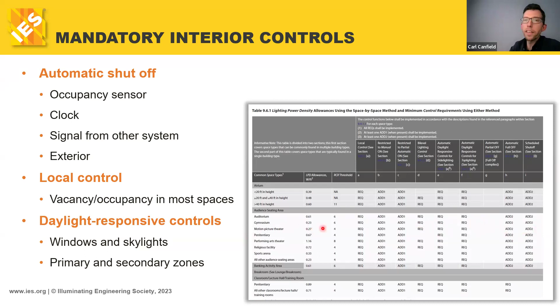I don't think we want to spend too much time here, but if you were to do a code compliance, actually dictating code compliance for a space, and if you had to use the interior lighting power allowance method, this is for all of your luminaires, all of your lights, the total wattage of those lights. It has to be under a certain threshold. You're only allowed so many watts per square foot for a given space type. And this is the method you use to dictate how that is.